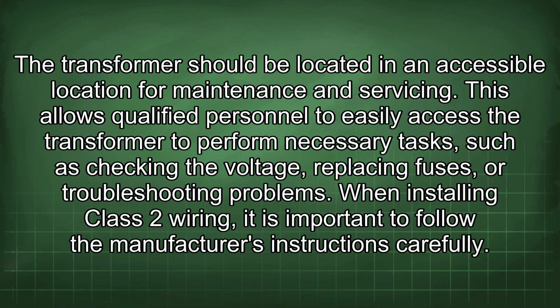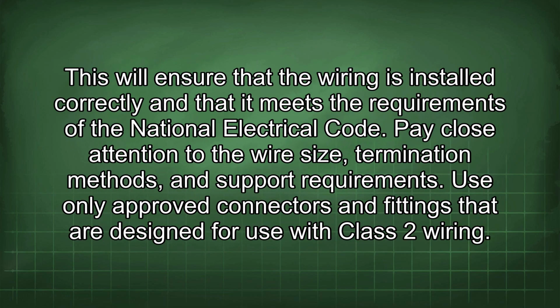The transformer should be located in an accessible location for maintenance and servicing. This allows qualified personnel to easily access the transformer to perform necessary tasks, such as checking the voltage, replacing fuses, or troubleshooting problems. When installing Class 2 wiring, it is important to follow the manufacturer's instructions carefully. This will ensure that the wiring is installed correctly and that it meets the requirements of the National Electrical Code. Pay close attention to the wire size, termination methods, and support requirements. Use only approved connectors and fittings that are designed for use with Class 2 wiring.